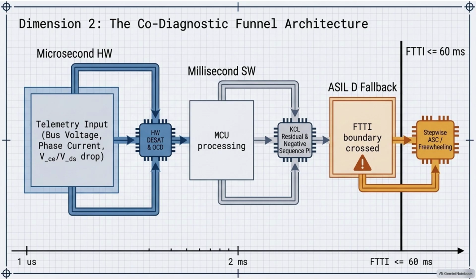Okay, but wait. 60 milliseconds sounds fast, but against an avalanche breakdown that happens in nanoseconds, that's an eternity. If the system waits 60 milliseconds to react to a shoot-through, there won't be a controller left to transition to a safe state. You're absolutely right, which is why the architecture is bifurcated into two distinct timelines. Oh, okay. You have the software brain operating on the millisecond scale, but you have the hardware reflexes operating on the microsecond scale. I see.